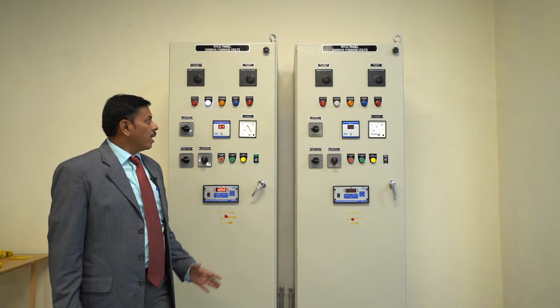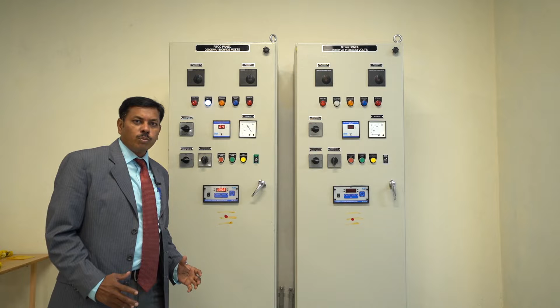As we have already said, our power distribution transformers are specifically customized and designed with copper windings with a maximum rated capacity of around 120%. We also need voltage control. Whenever there are voltage variations in the HT lines, we have the RTCC panel control system, from where we can automatically change the windings on the HT side, so that on load we can change the tap changing control systems and get the output voltage as per the requirement of Indian standards, which is 415 volts for the 3-phase system and 230 volts for the LT system.